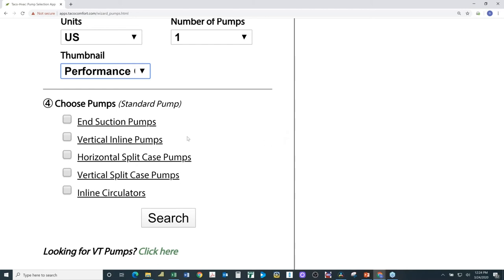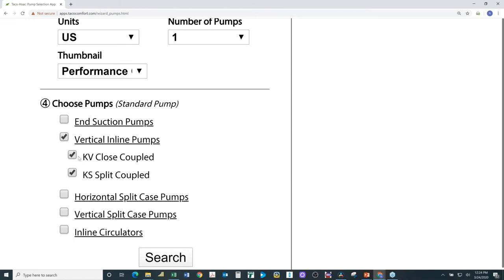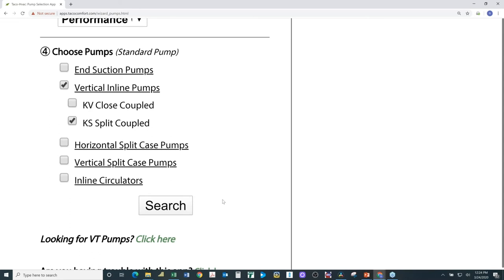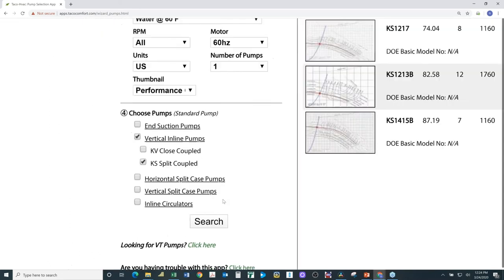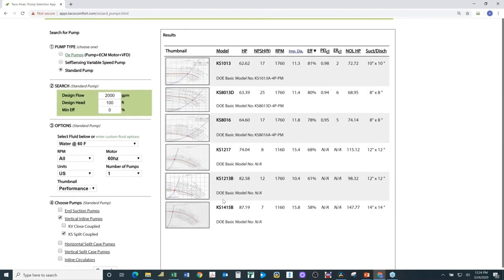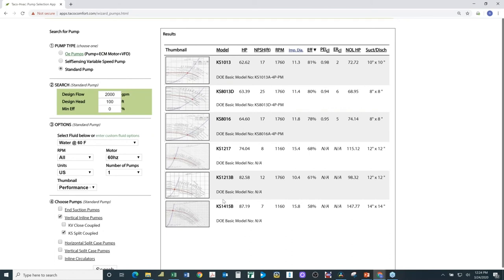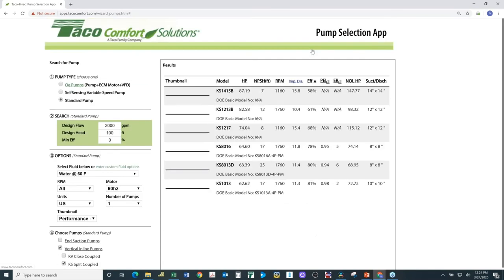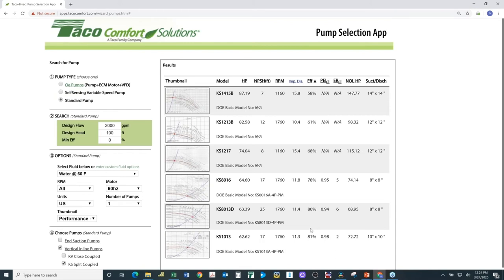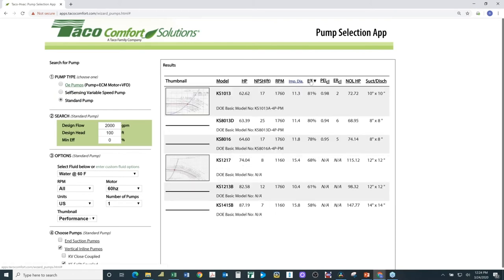For step four, I like vertical inline pumps today. I'll click on vertical inline, deselect KV, select KS pumps because of the split couple, and click Search. It populates the right side of the screen with all the different pumps that meet the criteria of 2,000 GPM and 100 feet of head — six options. It sorts the pumps from highest efficiency to lowest. If I click on the efficiency column, it resorts from lowest to highest, ranging from 58% up to 81%.